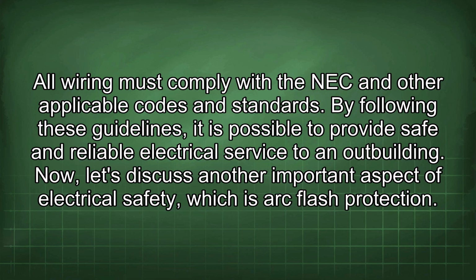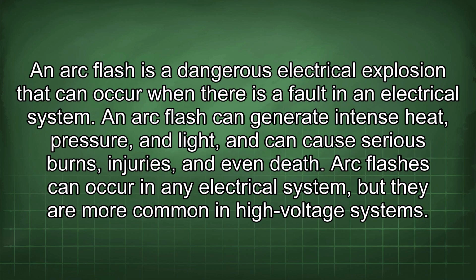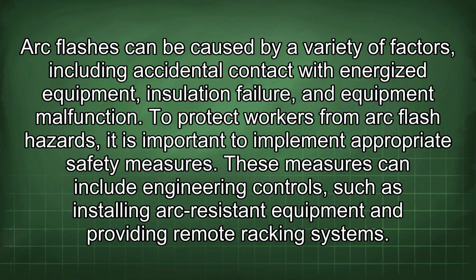Now let's discuss another important aspect of electrical safety, which is arc flash protection. An arc flash is a dangerous electrical explosion that can occur when there is a fault in an electrical system. An arc flash can generate intense heat, pressure, and light, and can cause serious burns, injuries, and even death. Arc flashes can occur in any electrical system, but they are more common in high-voltage systems. Arc flashes can be caused by a variety of factors, including accidental contact with energized equipment, insulation failure, and equipment malfunction.